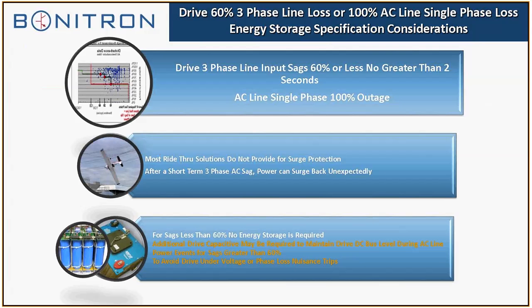Okay, a few more details about configuring, or what you need, for sag ride-through. As I said previously, we can go down to 60% for 2 seconds or 100% single phase. One thing to also consider is when you have a utility power event and the power comes back, there could possibly be a surge. So you may want to consider some sort of surge protection. The ride-through will not deal with any kind of surge protection. There are MOVs in there, but MOVs can only take a few hits. Especially with lightning strikes and things like that, there may be a surge coming back too. You might want to talk to the customer about whether that's an issue.